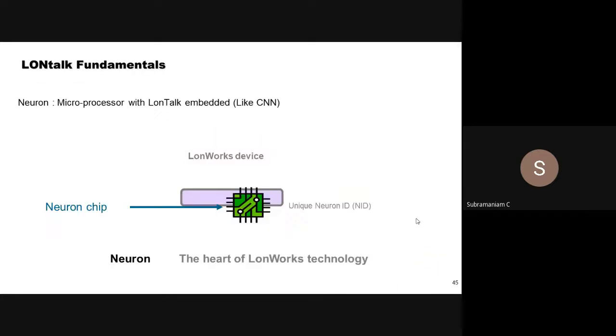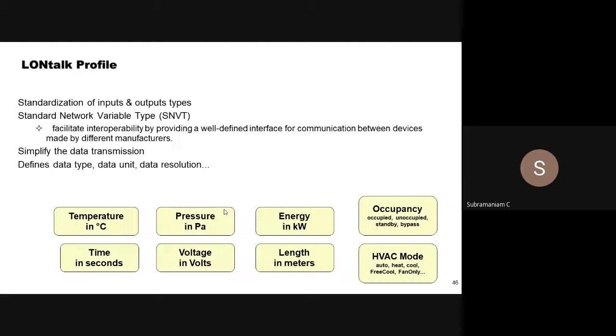Then LON is another protocol. A Neuron chip is embedded, and on that there is a Neuron ID on the device. For example, we buy a precision air conditioner from Emerson or APC or somebody else. If we buy it with the LON protocol, it means I can connect a wire and get my information to my BMS if it is LON compatible. At a brief level, there are profiles available. There is the SNVT profile, which we call the standard network variable type. It talks about temperature, pressure, and they define the unit also, so tomorrow we are not in the dark about what information we will get from that equipment, apart from its own standalone safety, which we talked about in unit control. So the profile is defined.